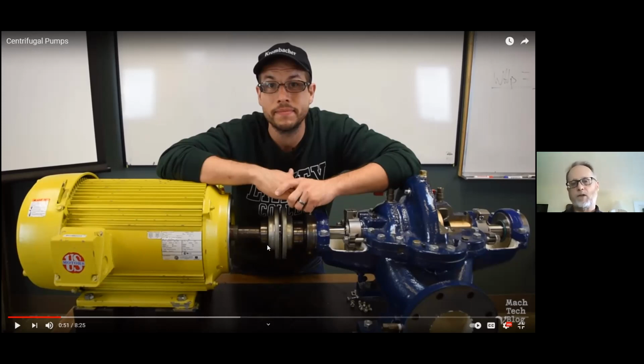And so the exam might ask the purpose of the coupling, and of course it's to be aligned so that it's true, so that there's no distortion. As the motor turns the shaft, it turns the shaft on the pump. The shaft for the pump passes through into the casing, so we have to seal it to prevent water from escaping. The seal will be either a mechanical or a packing type seal, the mechanical.